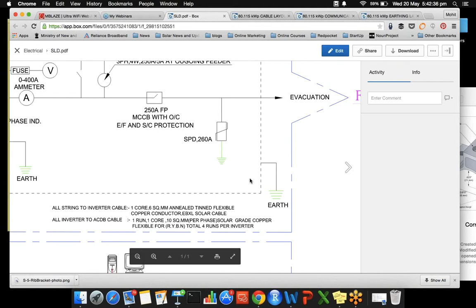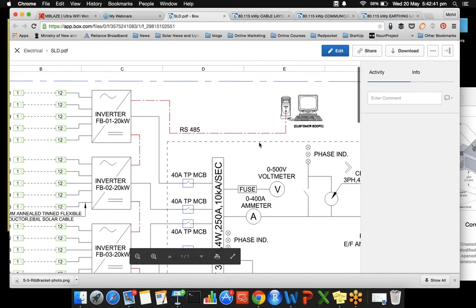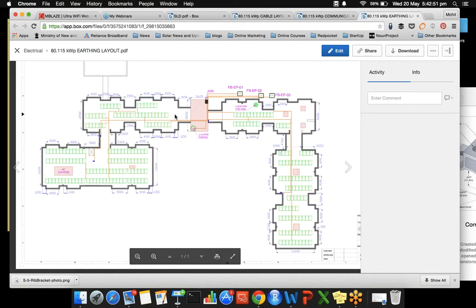The LA is marked here. From LA, the GI strips are connected to the respective earthing pit. As we can see in the SLD, the bus bar is connected to the earthing, then the ACDB box is connected to the earthing, and similarly, the other connections are made to the earthing as depicted here in the earthing layout. This is the complete route and the calculation of the GI strip which are required for designing the earthing.